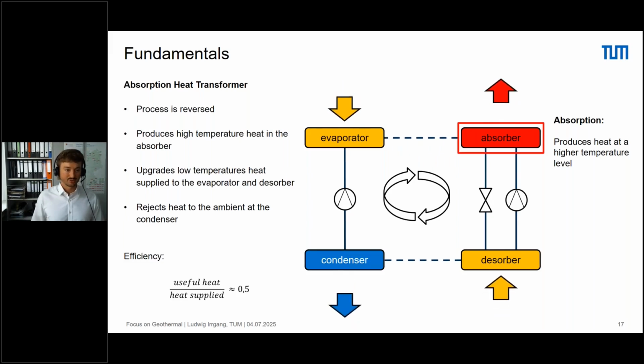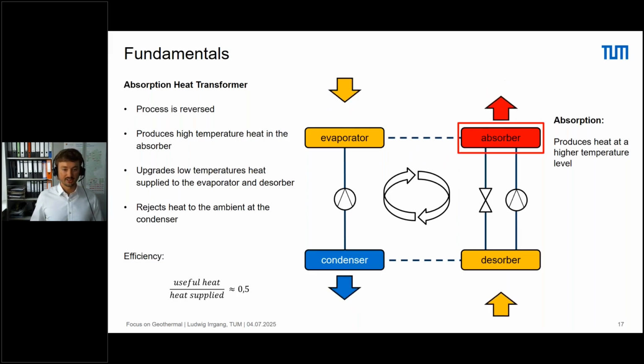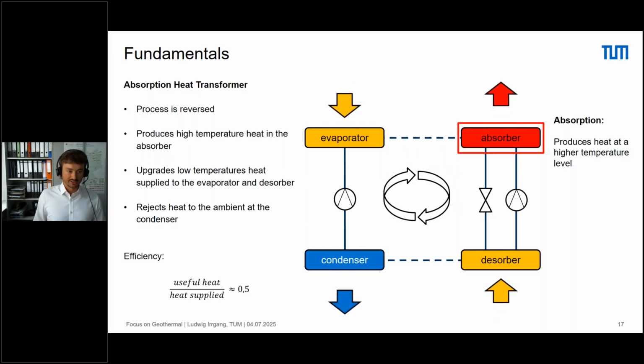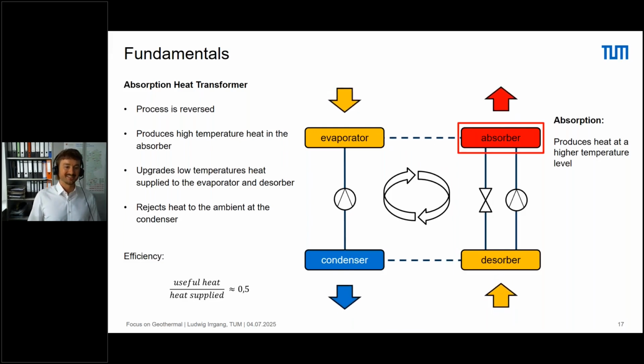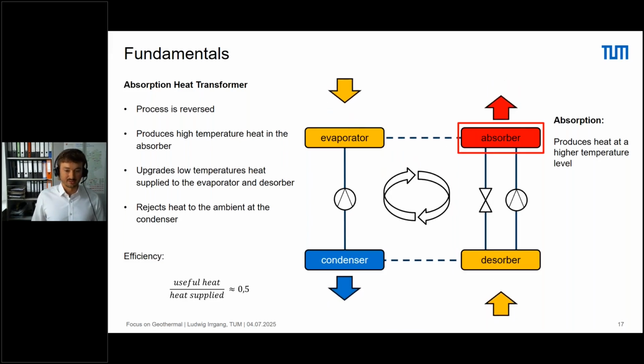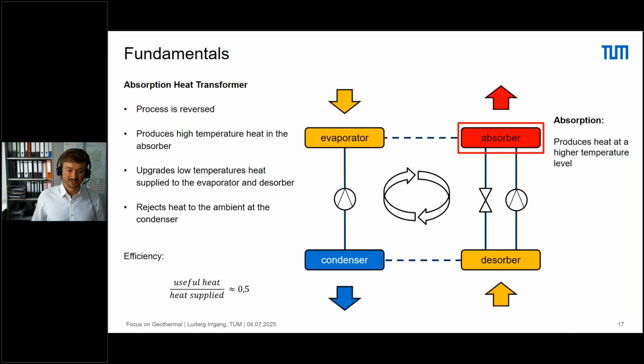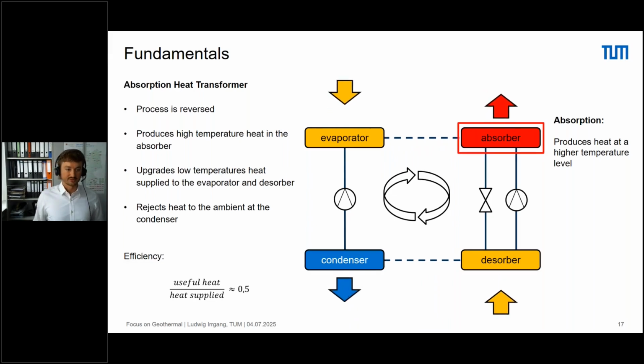So we can input heat at the evaporator and desorber at the lower temperature, and then use the absorber heat, for example, for the district heating network. We also have the condenser, which rejects heat to the ambient. But the good thing is that this condensation process is influenced in a good way if we have low ambient temperatures. So if we want to use the cycle in winter times, the low temperatures are very beneficial. The efficiency here is calculated as the absorber heat output to the heat supplied in evaporator and desorber, and peaks at around 0.5.